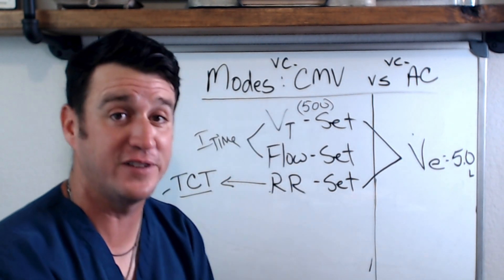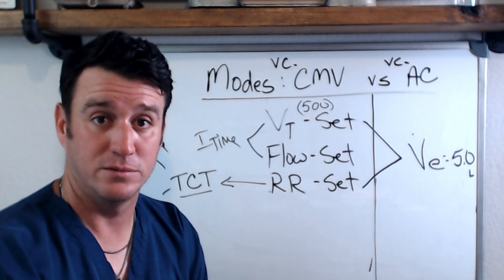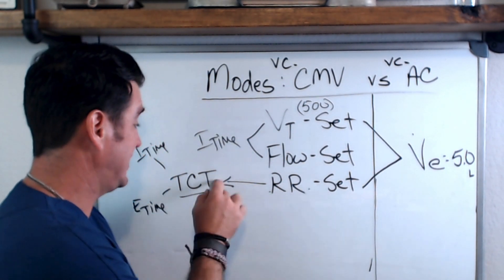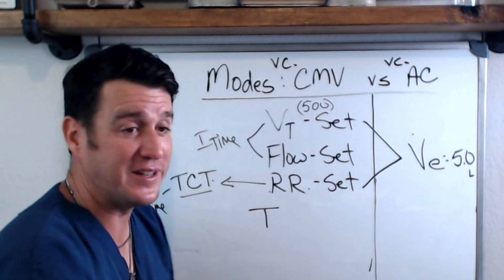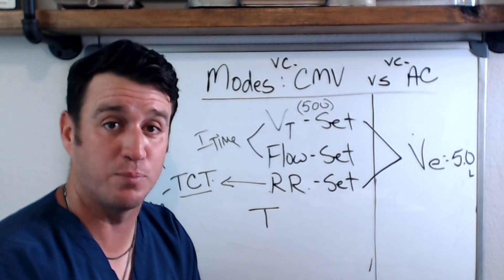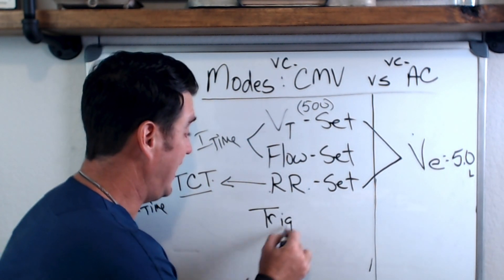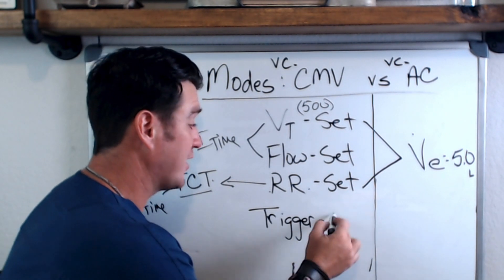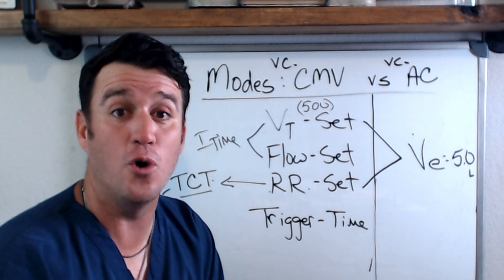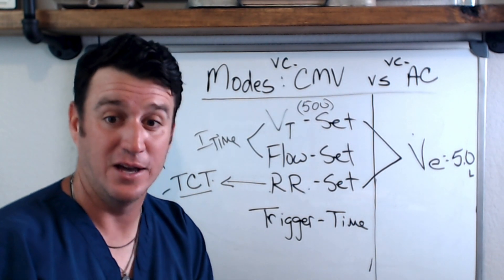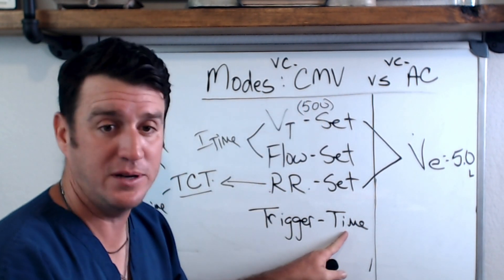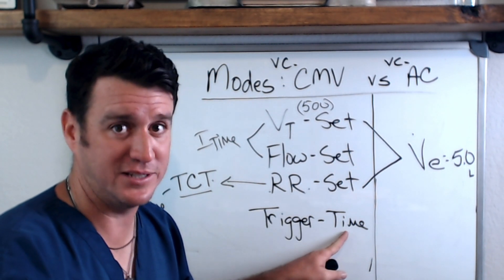Respiratory rate establishes total cycle time, which tells the ventilator how often to initiate inspiration. On a rate of 10 with a 6-second total cycle time, the trigger is time — and in CMV, our trigger is time and only time. Remember that — it's key and will make sense in just a moment.